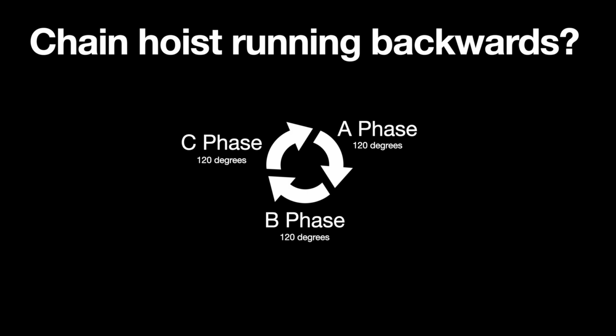Now, with the chain hoist, if it's running backwards, all you need to do to fix this is swap 2 of the phases. It doesn't matter which ones. The reason why this is important is it makes sure that up on the controller is actually up and down is actually down. And also, some of the older chain motors, the safety on them only work when the phase is correct. If you run your motor without a fully functioning limit, that could be catastrophic. Equipment could be falling from the air.